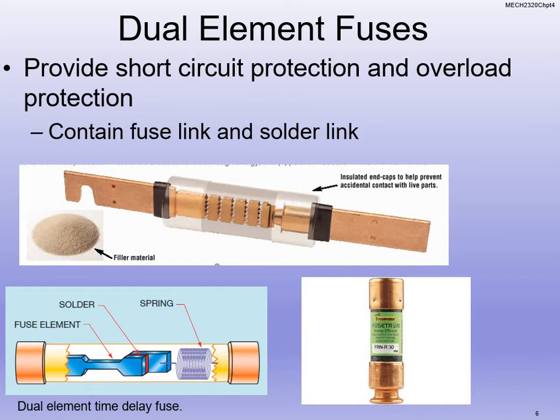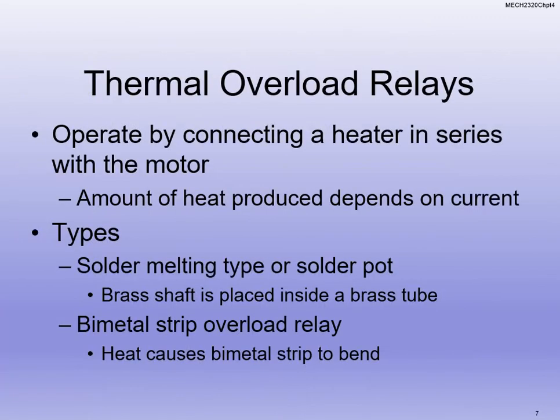We're still protecting equipment, but sometimes that equipment needs that inrush current to get going, to get the rotor going or something like that on a motor. So we don't want to trip a fuse every time, and it'll still allow it to run, because the temperature from the current won't be hot enough to melt the solder.